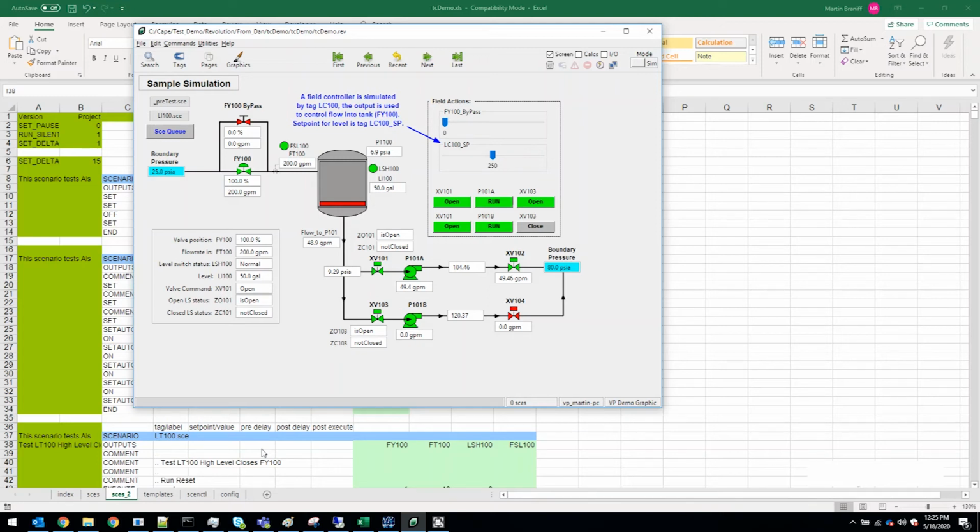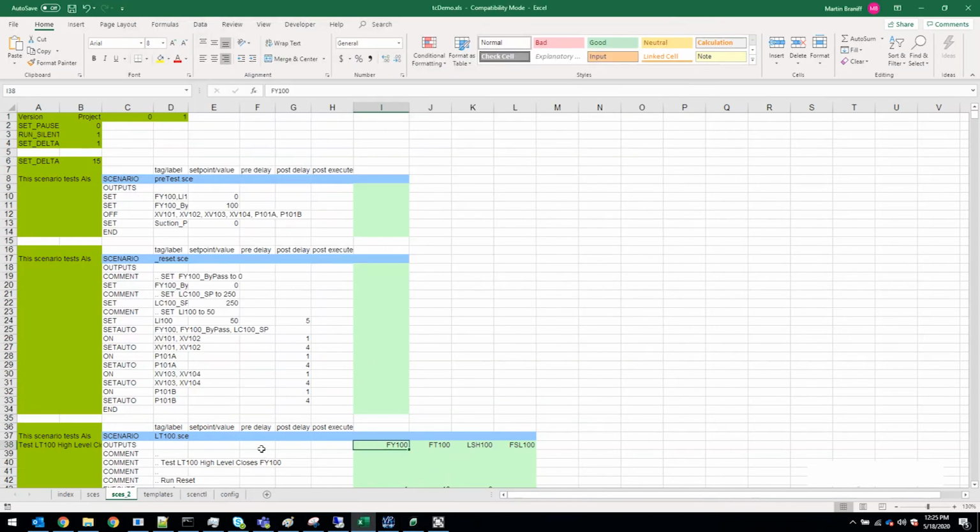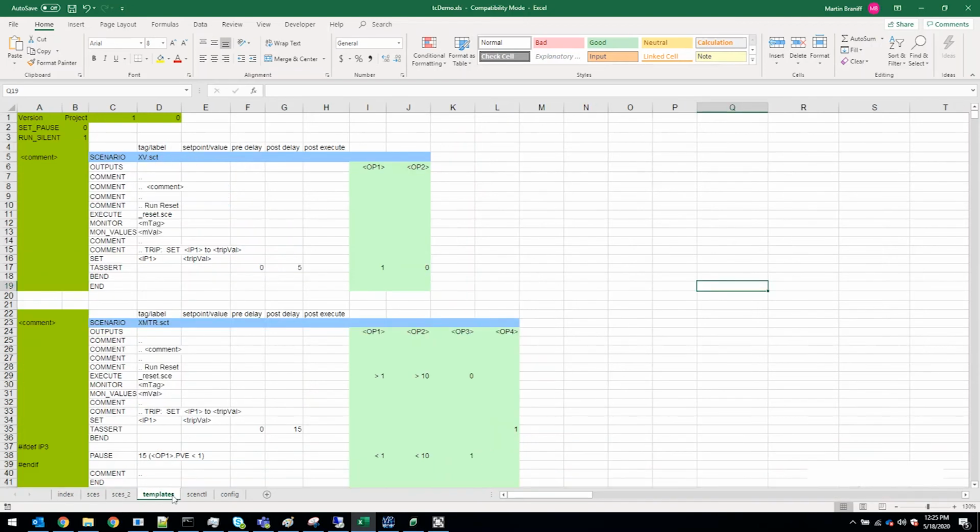In addition, these scenarios or cases can also be readily executed sometime in the future, in the event change is made to the control logic. This helps demonstrate that the changes being made have not affected the integrity and function of the original control code. The typical test plans can be put together using Excel, which provides an intuitive method of setting up the scenarios. These scenarios can be used to test 2 out of 3 failures, reset procedures and trip conditions, as well as many more situations.